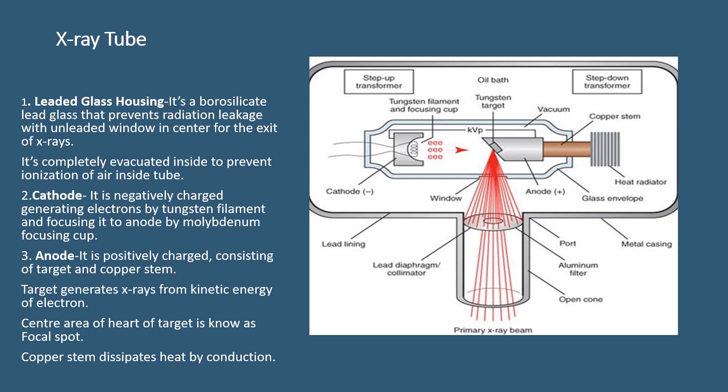The anode is positively charged and consists of a tungsten target and a copper stem. The tungsten target generates x-rays from the kinetic energy of electrons. The center area of the target is known as the focal spot. The function of the copper stem is to dissipate heat by conduction.